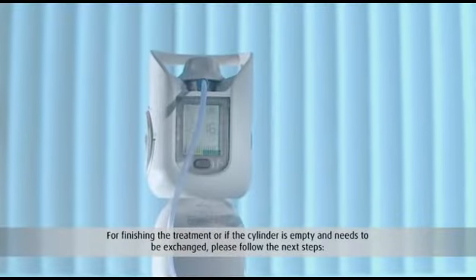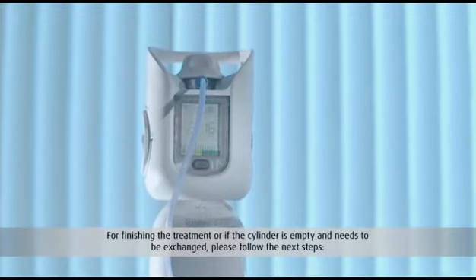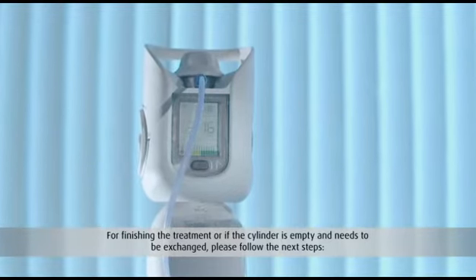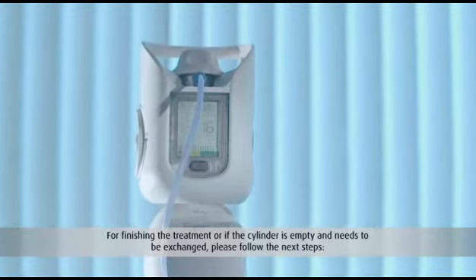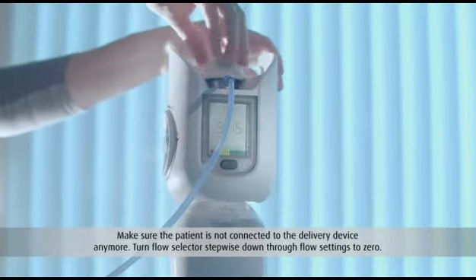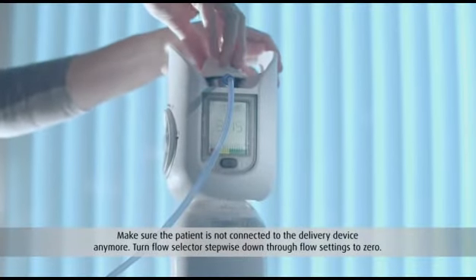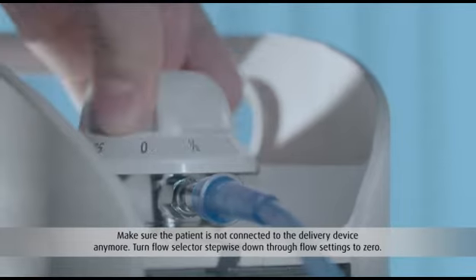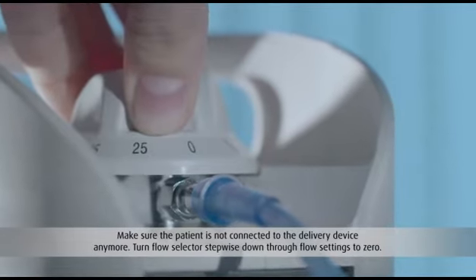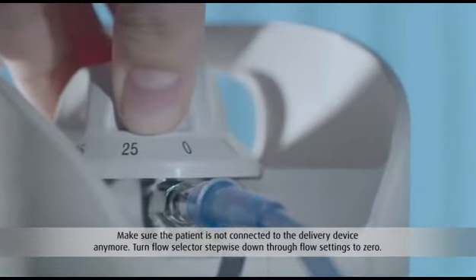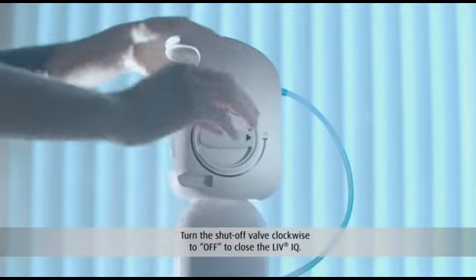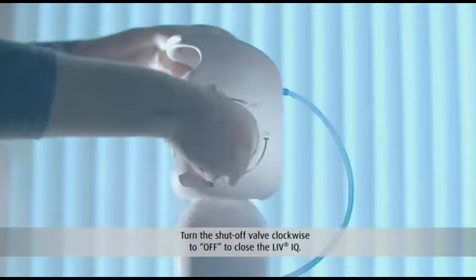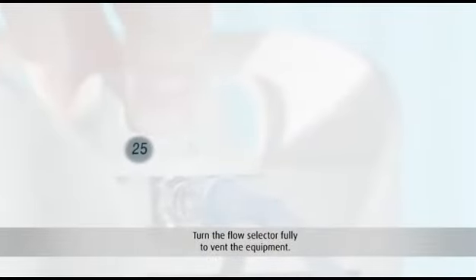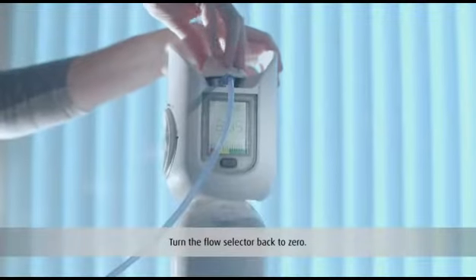For finishing the treatment, or if the cylinder is empty and needs to be exchanged, please follow the next steps. Make sure that the patient is not connected to the delivery device anymore. Turn flow selector stepwise down through flow settings to 0. Turn the shut-off valve clockwise to off to close the LIV IQ. Turn the flow selector fully to vent the equipment. Turn the flow selector back to 0.